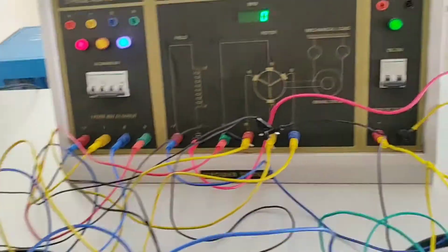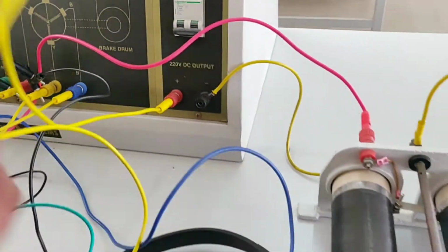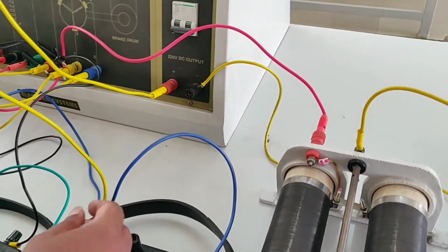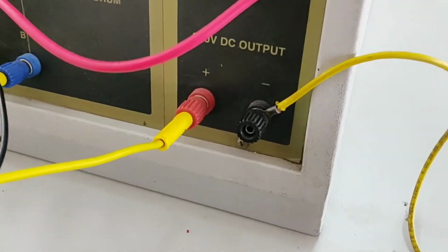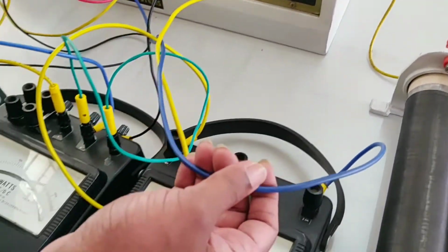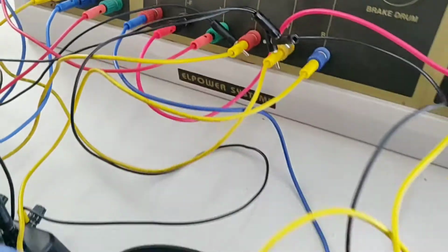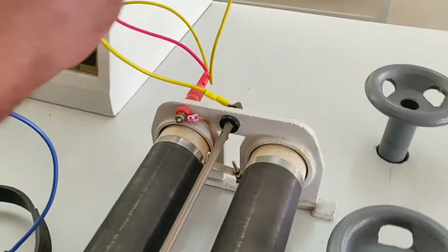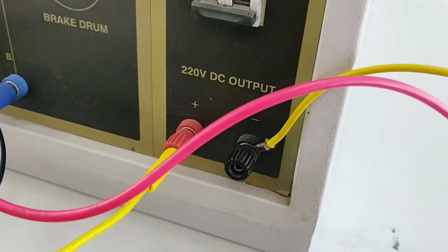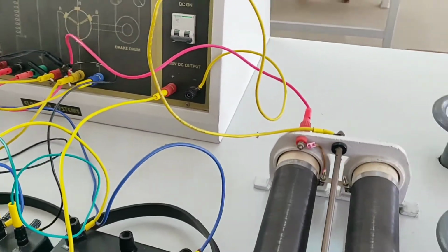You can go with the field circuit. The field circuit needs a DC supply. You have to give DC supply from the positive of the supply to the ammeter positive, and then from the ammeter negative to the plus F of the field, and then minus F of the field is connected to the rheostat, where you can have control over the resistance of the circuit, and the other end of the rheostat is again fed to the supply. So this is the connection.